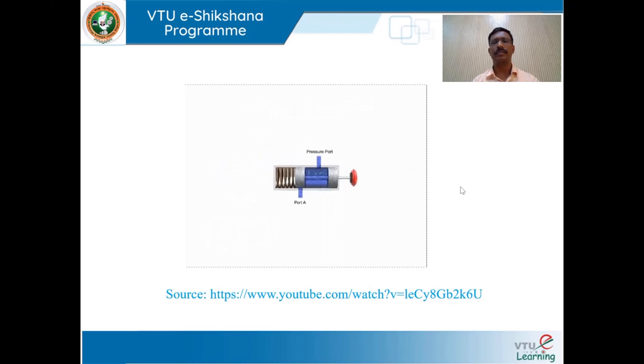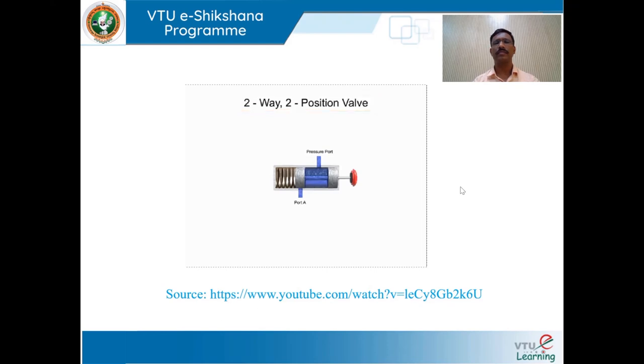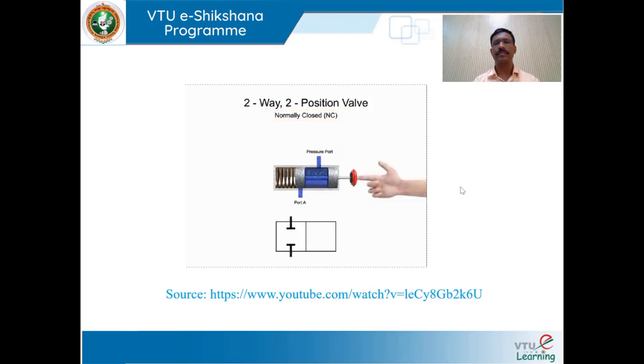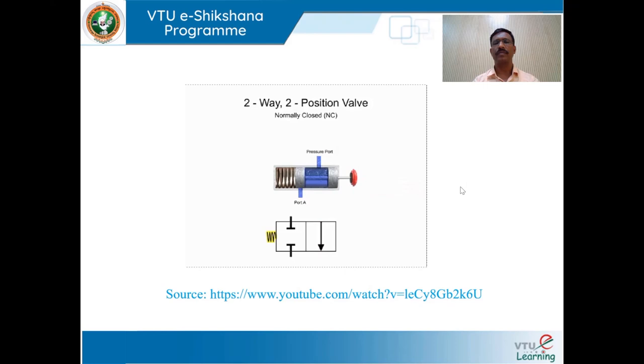Here is a similar two-way two-position valve. In the normal non-actuated position, both ports are blocked, making it a normally closed valve. When actuated, fluid flows from the pressure port to port A. A spring returns the valve to its normally closed position and a push button actuates it to the open position — making this a two-way, two-position, normally closed, spring return, push button operated valve.